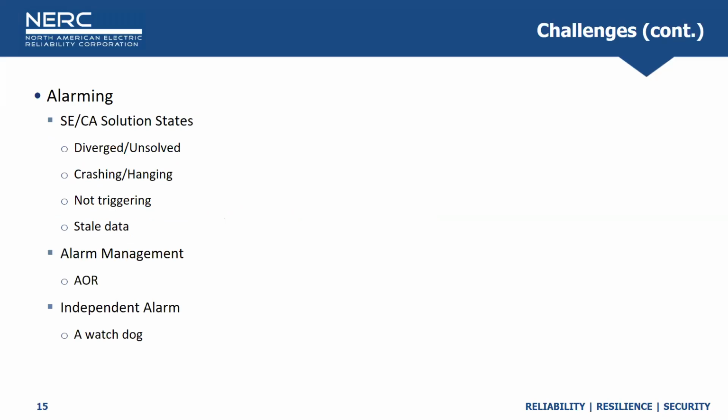The other challenge for us is alarming. Alarms don't cause the problem, but if alarms are not configured correctly, that will make the event worse. For example, if an event happens and I get an alarm, I can jump in and get it solved as soon as possible, within 30 minutes. But if the alarm was not configured or set properly, I may not get an alarm, so I don't know what's going on. The event will last longer and longer, grow bigger, and that's worse, it becomes a huge event.